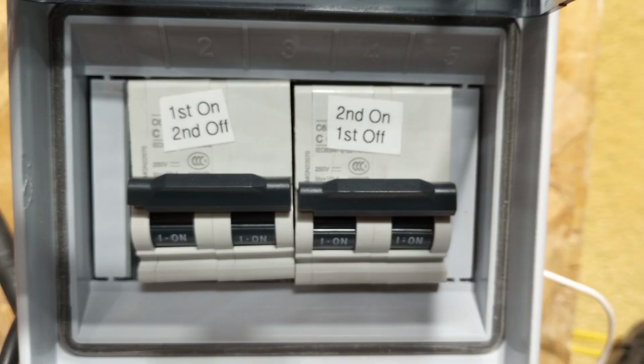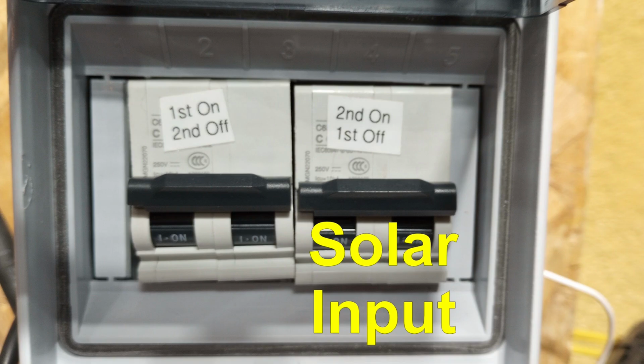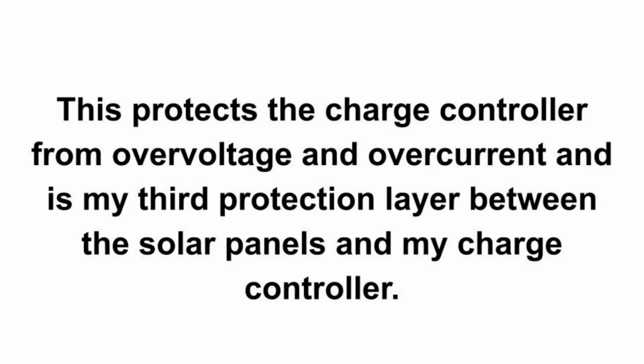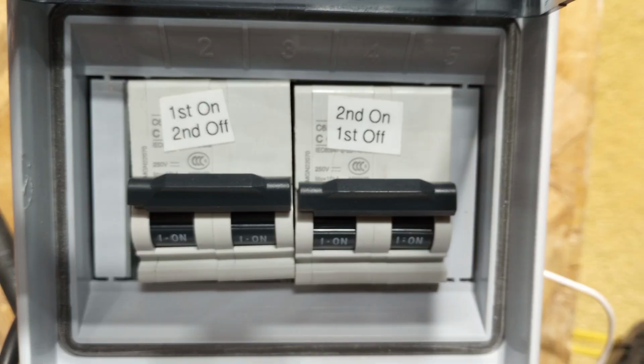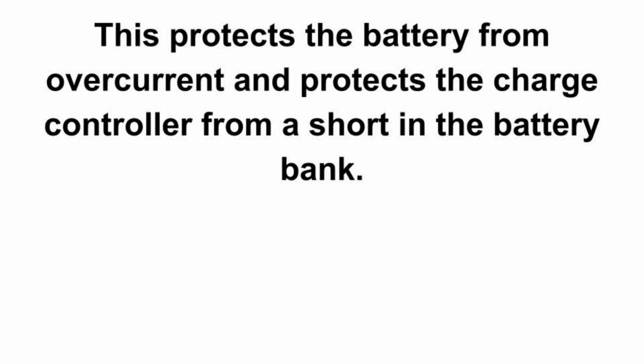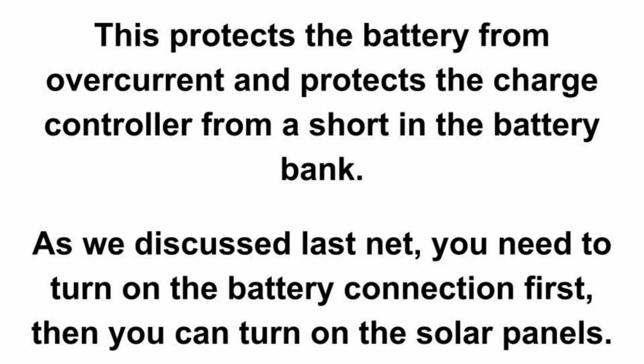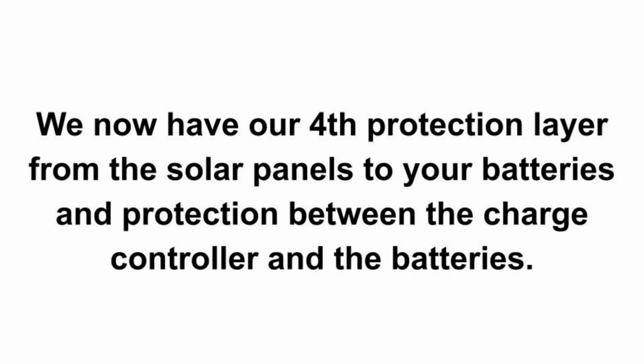At the charge controller, I have another breaker disconnect switch for the solar power into the charge controller. This protects the charge controller from overvoltage and overcurrent and is my third protection layer between the solar panels and my charge controller. Now, as the power comes out of the charge controller directly to the battery bank, there is another breaker disconnect switch. This protects the battery from overcurrent and protects the charge controller from a short in the battery bank. As we discussed last net, you need to turn on the battery connection first, then you can turn on the solar panels. We now have our fourth protection layer from the solar panels to your batteries and protection between the charge controller and the batteries.